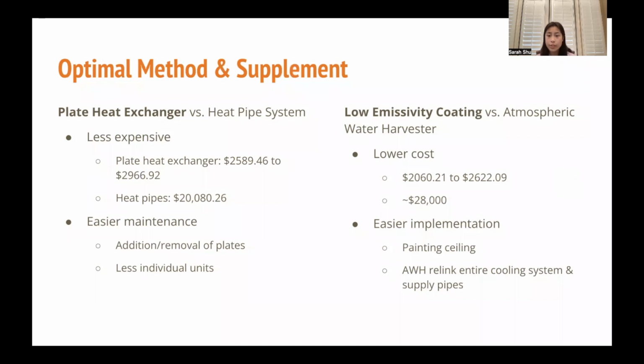It was also easier to maintain because the device can be easily adjusted by adding or removing plates. Furthermore, it is a lot less tedious to set up the plate heat exchanger since it has fewer units to install. Between the two supplemental methods, the better suited option is the low emissivity coating. It costs less and has a relatively easier implementation process. So rather than having to relink the entire cooling system and supply of liquids, the coating simply needed to be applied to the surfaces.